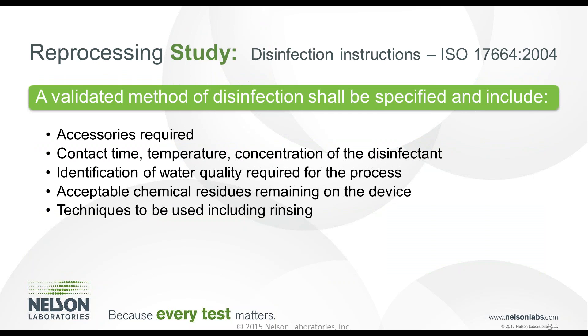For ISO 17664, disinfection should include a manual disinfection process if the devices are manually cleaned, and there should be an automated disinfection process if the devices are put in an automated washer disinfector.